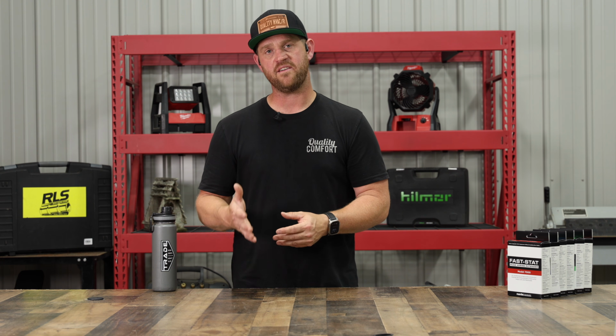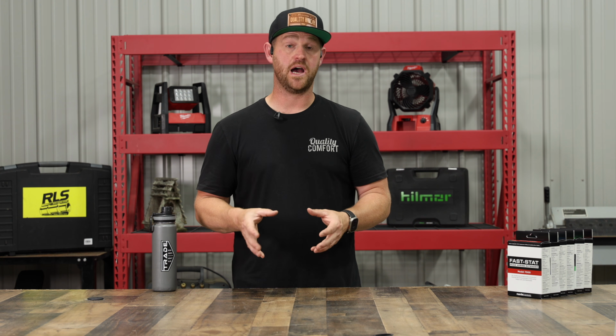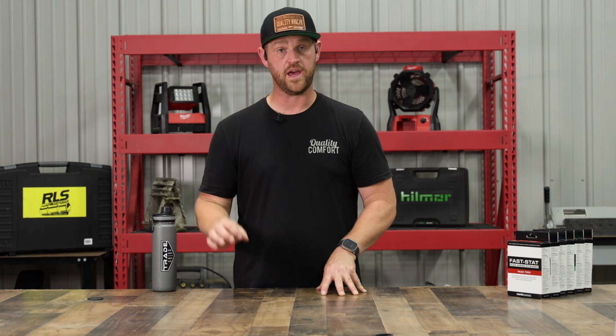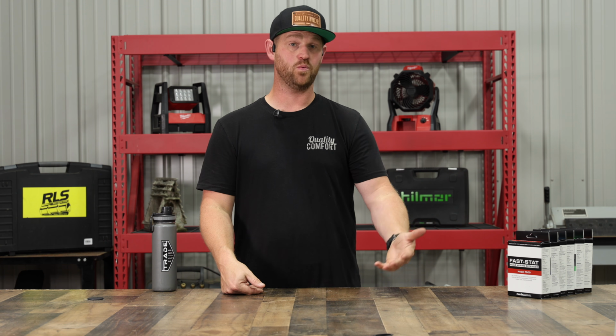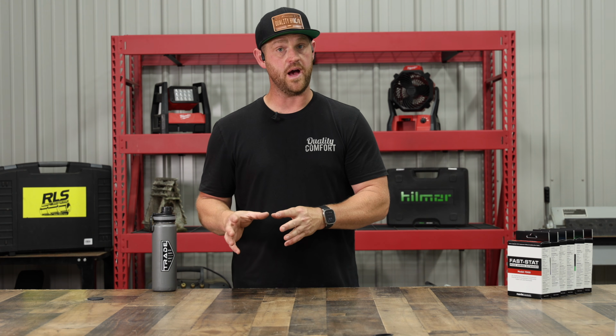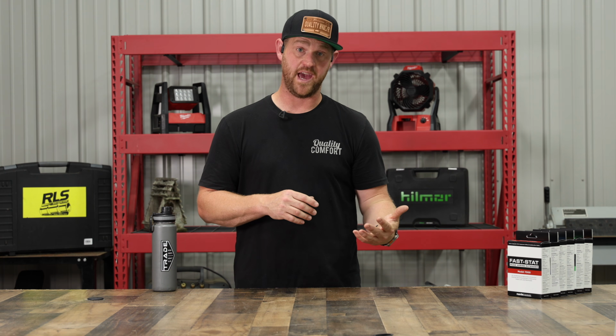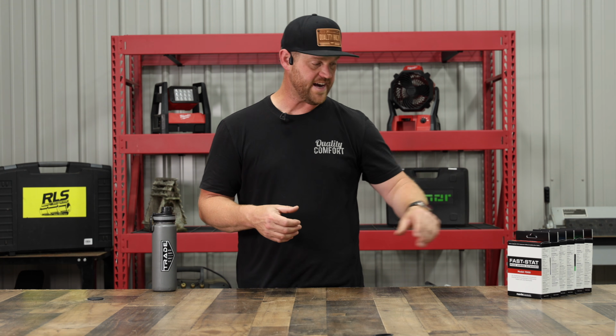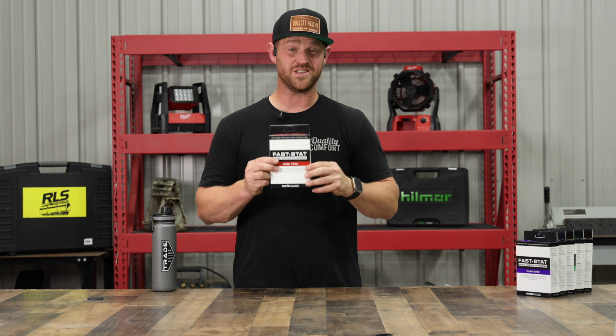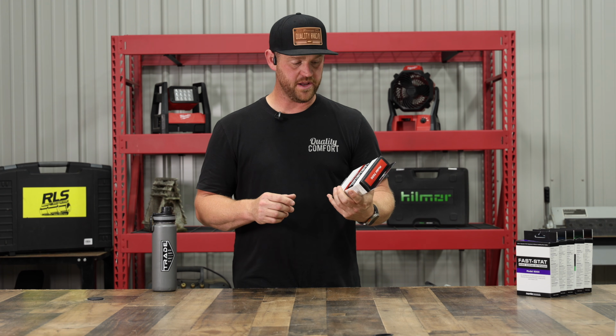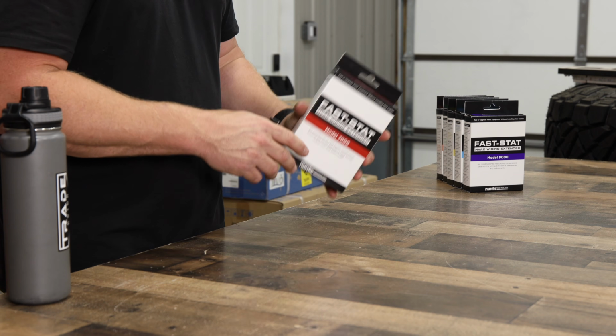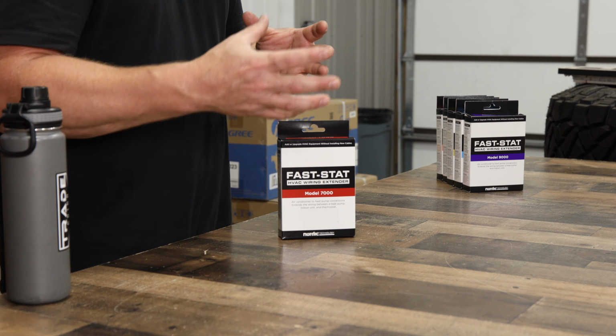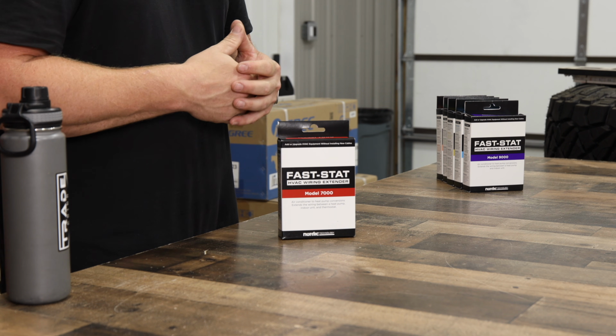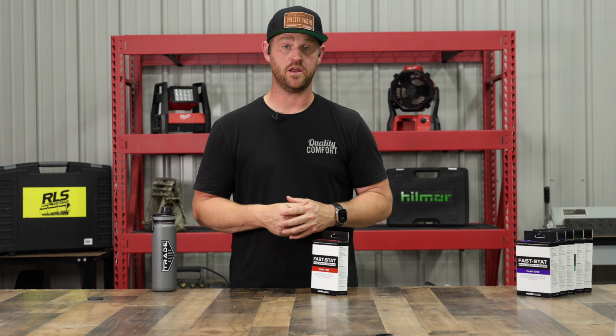Your thermostat cables are already going to be there. The only struggle that we have with that in the field is that sometimes we won't have enough conductors in the low volt cable, because we might need one or two more depending on the equipment we're installing. But there is a workaround. If you can't pull a cable, there is a company called FastStat. FastStat offers six different options. Depending on the situation, basically what it can do is add conductors wirelessly to your system, so you can still have the functionality that you're looking for.